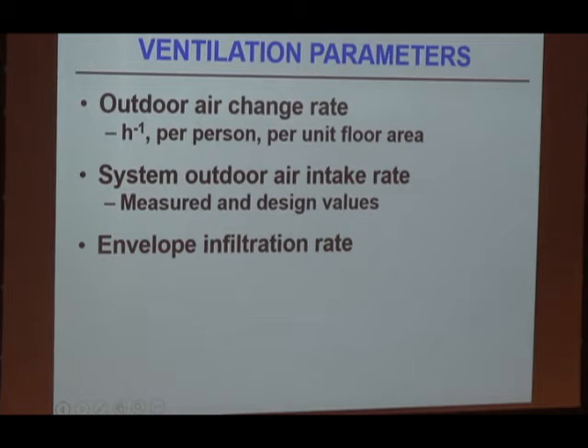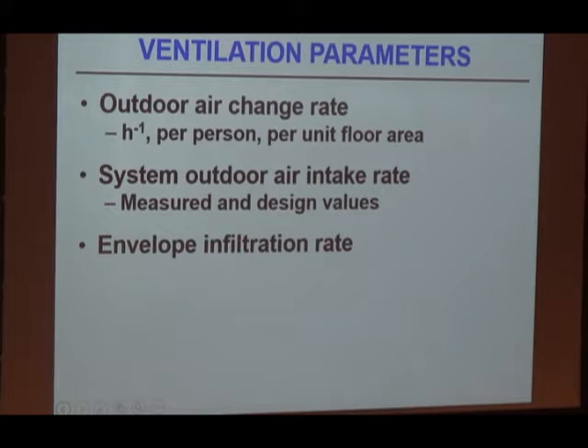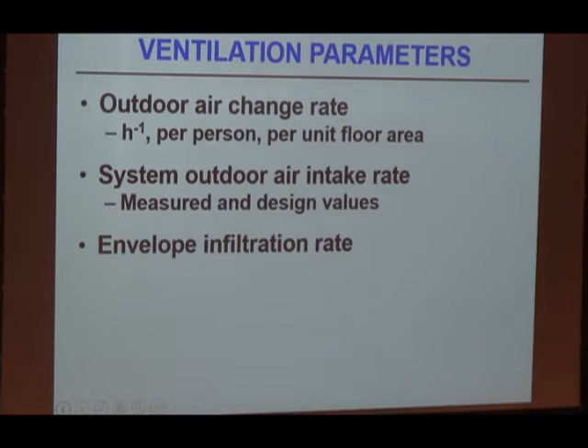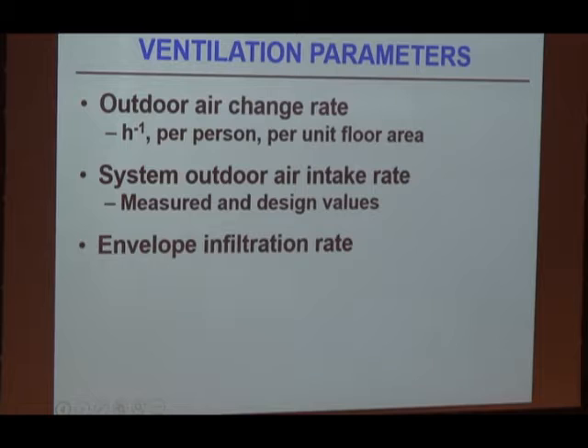There are three primary quantities to measure: the outdoor air change rate — the total rate at which air enters the building, including what the system brings in and leakage through the envelope; the amount of air brought in by the ventilation system; and the envelope infiltration rate. It's important to understand the design value — what the system is supposed to be doing — to fully interpret your measurement results.